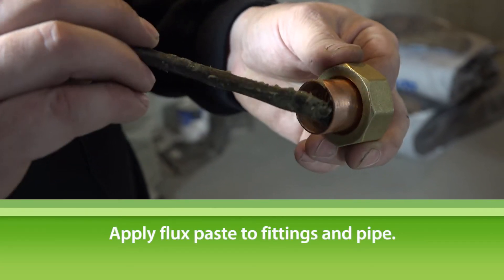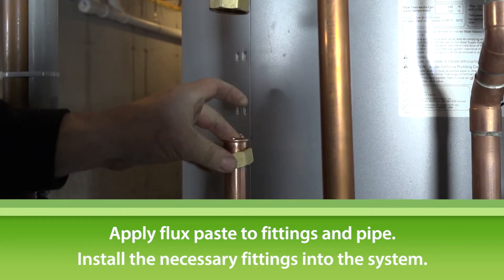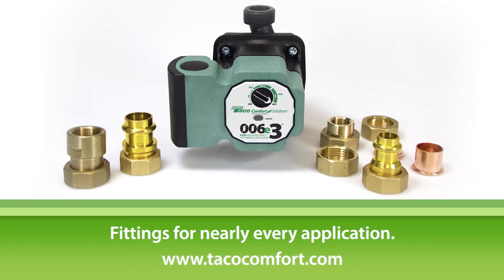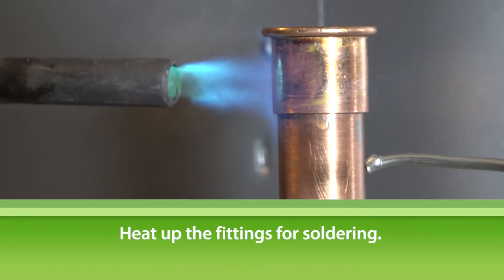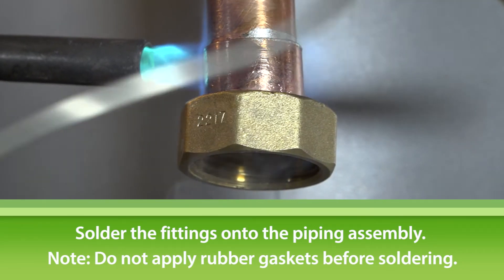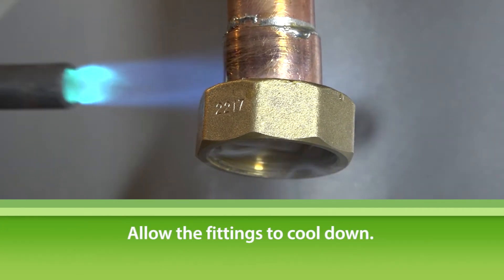Apply flux paste to your fittings and pipe, then install the necessary fittings into the system. Taco offers fittings for nearly every application, so you should have no trouble finding the right ones. Now, heat up your fittings so that they're ready to be soldered. Solder the fittings onto your pipes without the rubber gasket. Wait a few minutes for the fittings to cool down.